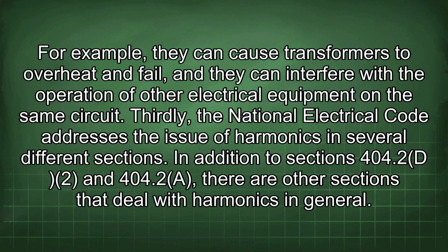For example, they can cause transformers to overheat and fail, and they can interfere with the operation of other electrical equipment on the same circuit. Thirdly, the National Electrical Code addresses the issue of harmonics in several different sections. In addition to sections 404.2 D2 and 404.2a, there are other sections that deal with harmonics in general.